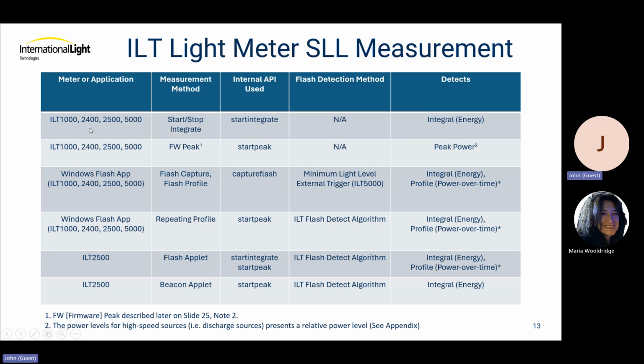But all the meters have a very simple start, stop, integrate mode. And this is akin to, if you've been doing this for a while and you remember the ILT 1700, heck, you might even still have one hanging around. It was start your flashing source, hit start, hit stop, get answer. And that's what this one does. And it gives you the energy.